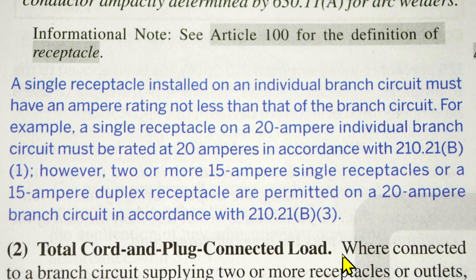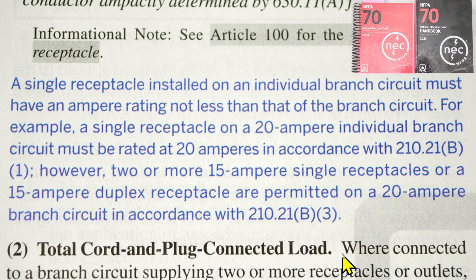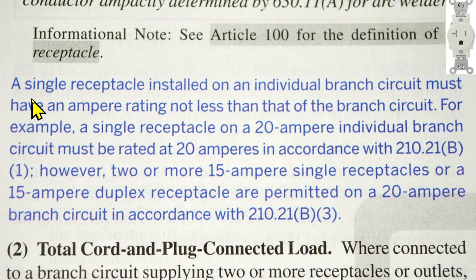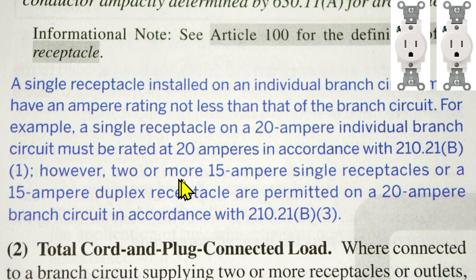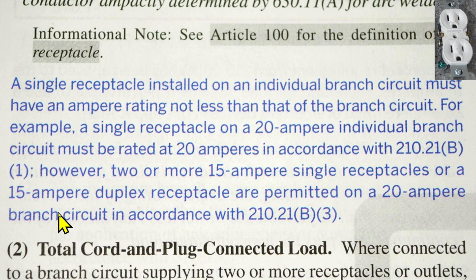A duplex receptacle is an example of a multiple receptacle that has two receptacles on the same yoke or strap. On your left is a 20 amp single receptacle and on your right is a 20 amp multi-receptacle, more specifically called a duplex receptacle. This explanation in blue is from the 2023 NEC handbook, which adds explanations, photographs, and drawings to help you understand the codes. A single receptacle on a 20 ampere individual branch circuit must be rated at 20 amperes per 210.21(b)(1). However, two or more 15 amp single receptacles or a 15 ampere duplex receptacle are permitted on a 20 ampere branch circuit per 210.21(b)(3).